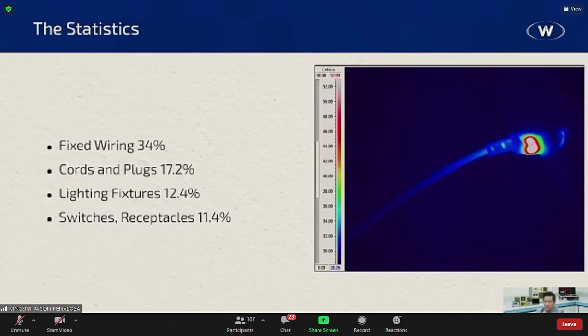Again, why? Because it usually happens that when we pull out the plugs, we pull from the cable and not the plug itself. You also have lighting fixtures, which make up 12.4%. However, these are usually high bay lighting, the ones with lamps and high-powered ballasts. The LEDs are not as susceptible, but it really depends on the kind of LED drivers you have. If those LED drivers are not well built, then they can cause fires as well. Switches and receptacles, because when you have a high resistance contact between your switches, receptacles, or circuit breakers, they introduce thermal effects as well, and they can catch on fire.